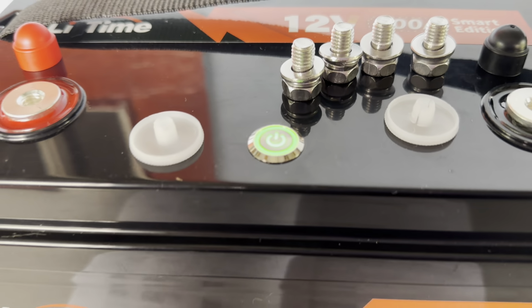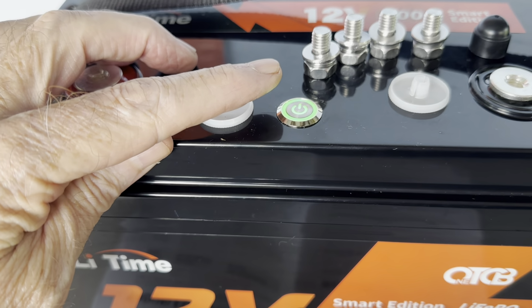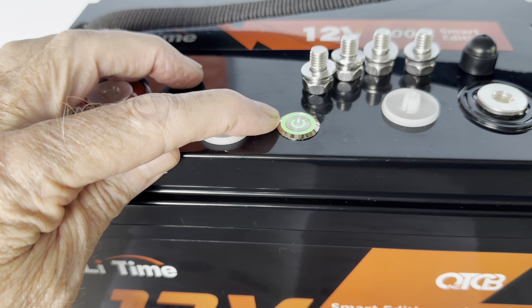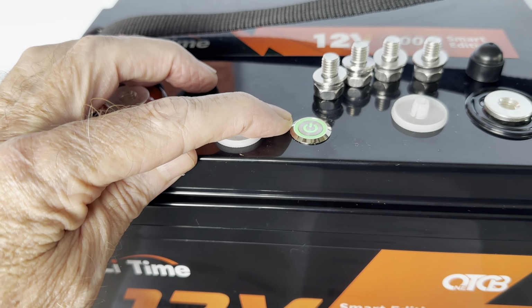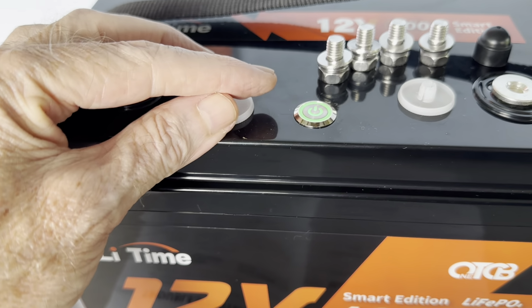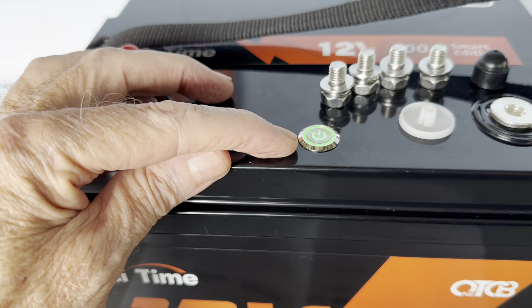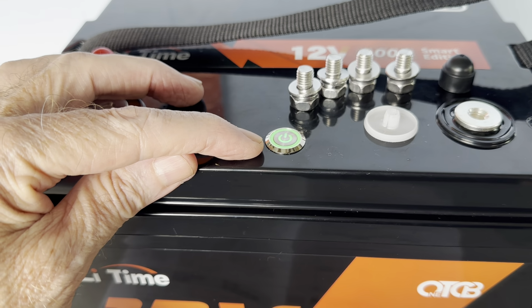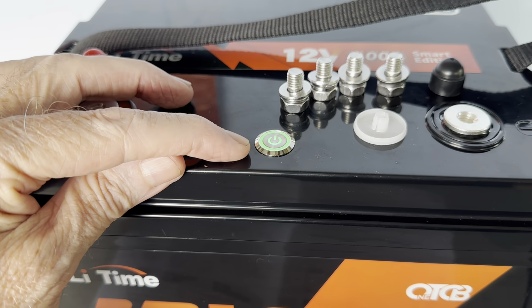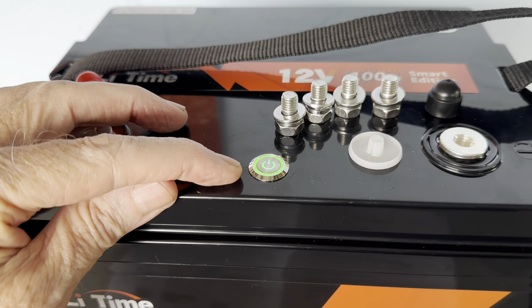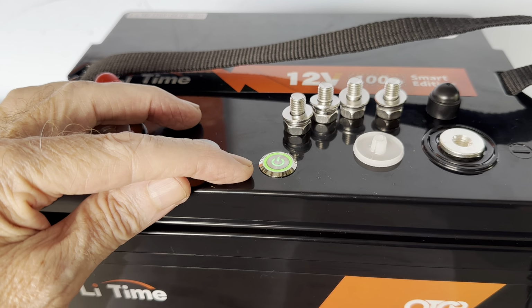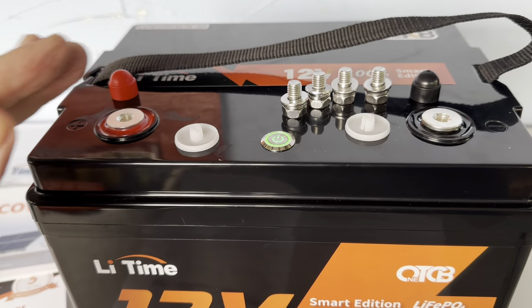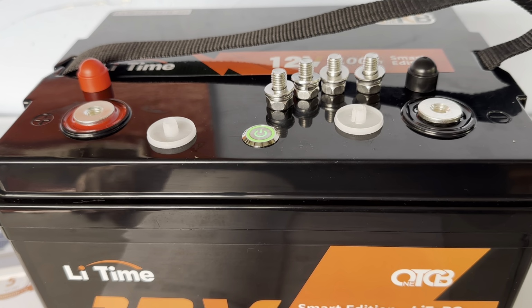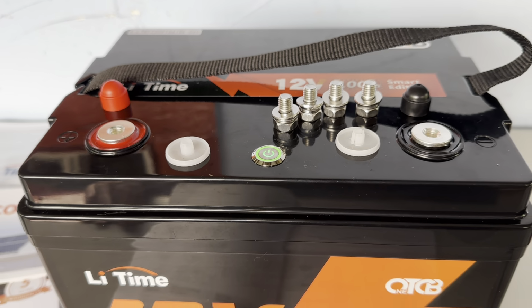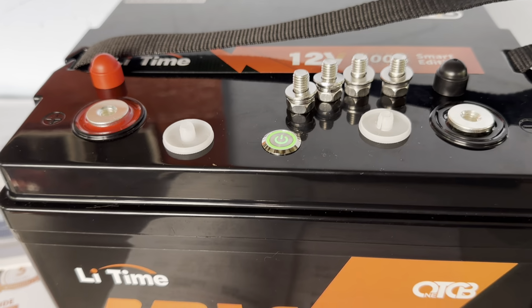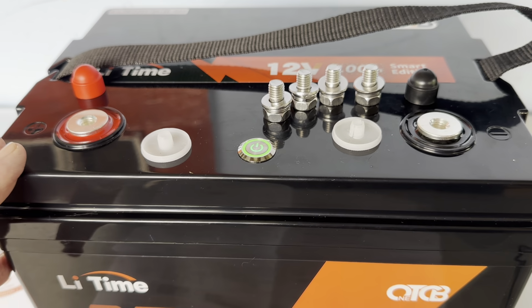And one more thing I'll point out is if this was flashing orange, it could be indicating the end of the battery life. If you've had more than 5,000 discharge cycles or more than 12 years cumulative operating time, depending how you were using it, if you were working it hard with lots of 100% depths of discharge. If you're working with a lot less depth of discharge, this thing is boasting the possibility of 15,000 cycles. So that would be a lot more years. So out here we try to cycle these batteries no lower than the 20%, basically from 80% to 20% is what we shoot for to get the maximum life out of these batteries. We've been able to do that so far.